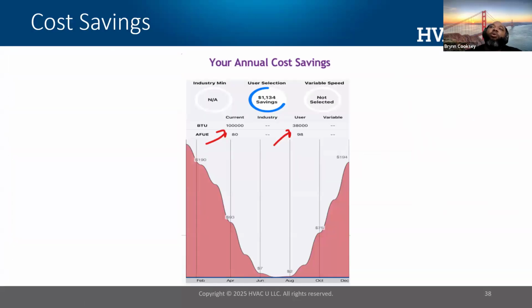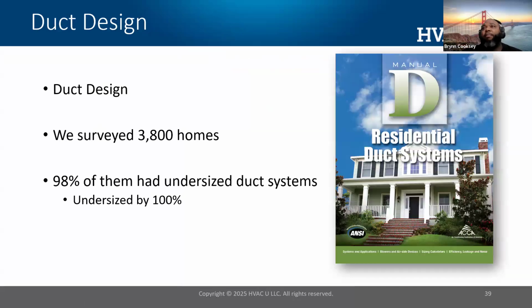Okay? When you properly size it, this is a tool that we use called Emerson eSaver. And it basically takes the fuel rates inside of your area and it leverages the existing system you're going from to the system you're going to. So if I was to go from a 100,000 BTU furnace to a 38,000 BTU furnace, these are fictitious. And the savings in a year due to properly sizing, with the fuel rates in this area from this calculation, came up to almost $1,200. So properly sizing the system, you can see, will create less carbon emissions and it'll also reduce your bill.